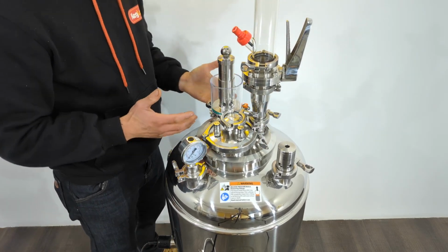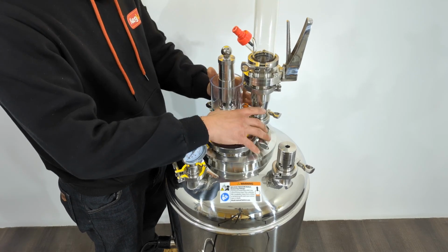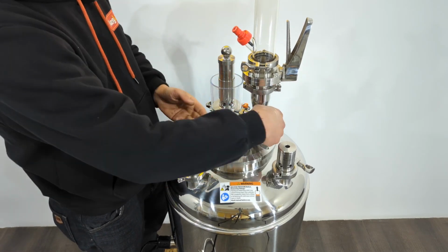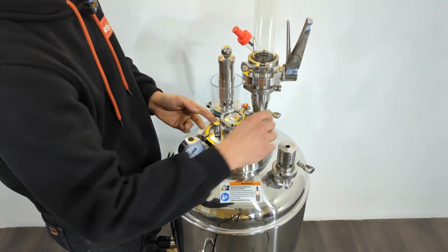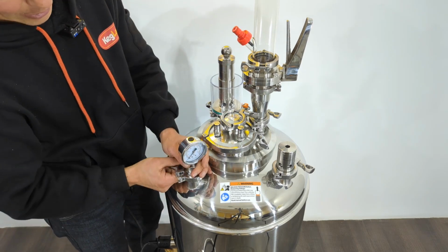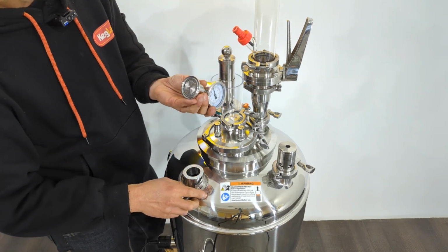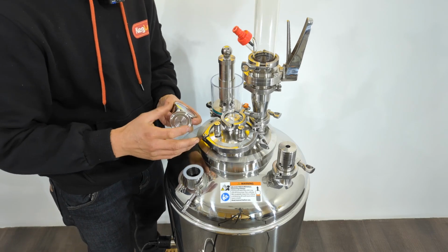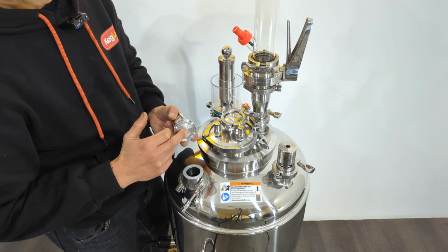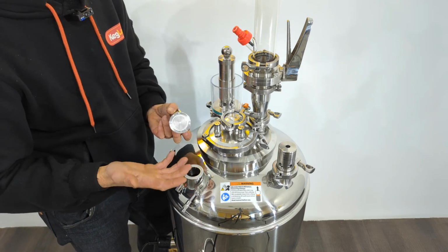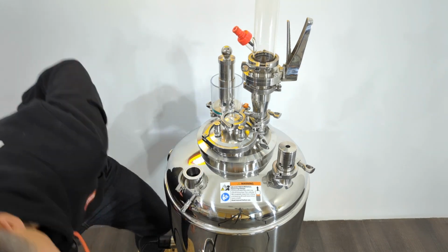It's also just a big enough size to fit all these extra ports on top. We've got a number of 1.5-inch TC ports, including one for the pressure gauge. As you can see, we're using a diaphragm pressure gauge, which is the highest possible standard since it's the most sanitary option. Good to see that on there.